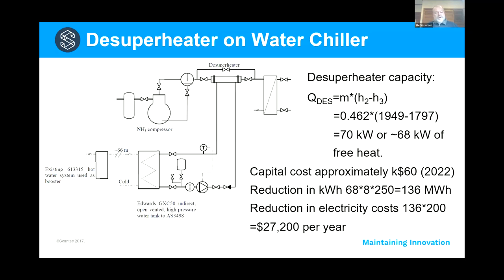So I reduced that by 2 kilowatts for a couple of reasons. First of all, the pump costs a bit of power. And also the desuperheater has a pressure drop. And when we cause a pressure drop in the discharge line of the compressor, we increase the power on the refrigeration compressor marginally. So these couple of kilowatts account for those losses. I do concede that we have a gain on the condenser. In other words, the condenser that sits downstream of the desuperheater doesn't quite have to work as hard, but I've sort of ignored that in this comparison.